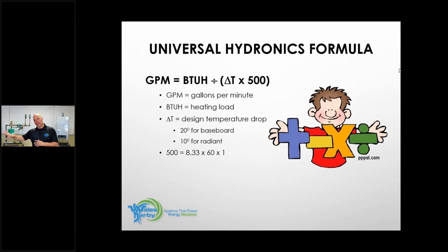And then we have the other side of the coin where we may need some antifreeze in the system, whether I have an air handler in the attic, whether I have a radiant system that's tied to the boiler, whether I have pipes that go out into my overhang and go up to the second floor that freeze every so often. It's annoying, so I put antifreeze in the system. That changes things a little bit. Antifreeze wants to reject the absorption of heat. That's why we use it in our automobiles, right? We want to take that heat out of the engine and get rid of it through our cooling system.